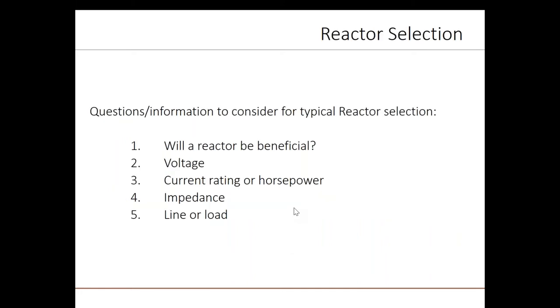Here are the main pieces of information required for reactor selection. In most cases, a reactor can provide a benefit, and we will discuss some of those benefits later in the presentation. You need the voltage of the VFD or motor. Third, you need the current rating or horsepower of the motor. You also need the impedance, which is typically expressed as a percentage or per unit value. And lastly, you need to consider whether the reactor is to be applied on the line or input side of the VFD, or the load or motor side of the VFD.